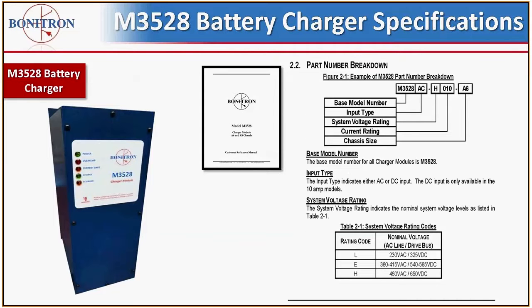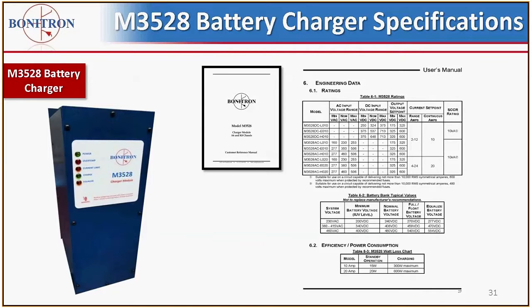In the manual, you'll have a part number breakdown that will help you understand what the unit capabilities are. And you also, once again, have the line voltage designators, which are in the part number, which are very important to ensure we have specified the right type of charger. This shows the charger model numbers and capabilities. Also battery bank values and a watt loss chart too, if you're putting the unit into an already established cabinet with the rest of the ride-through.